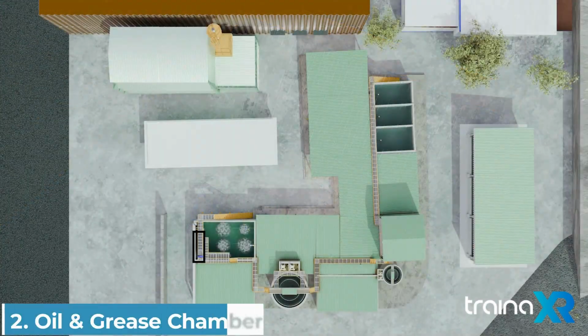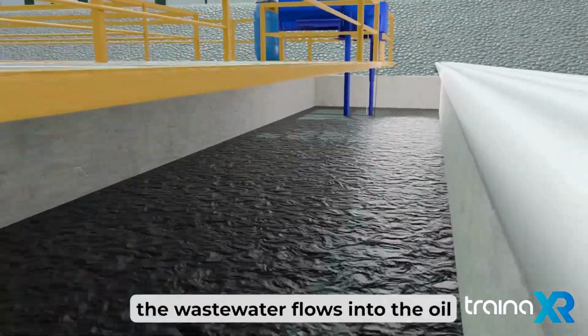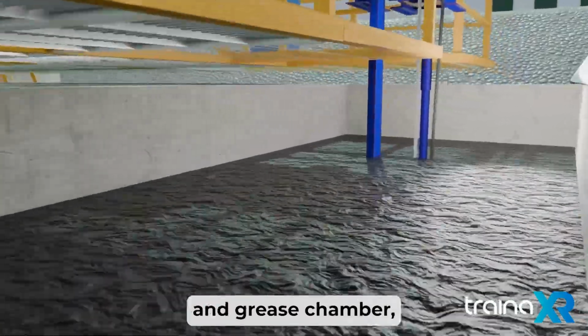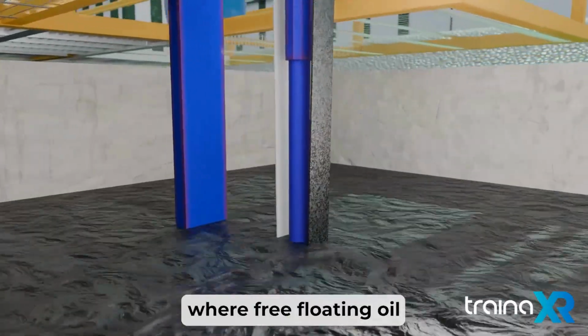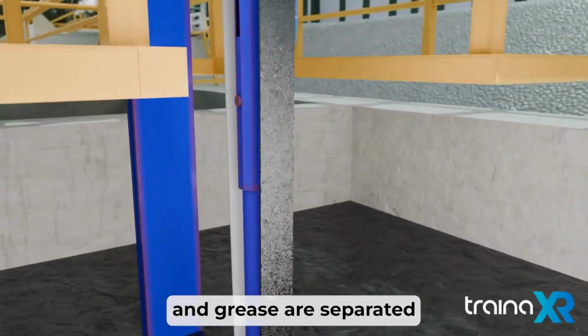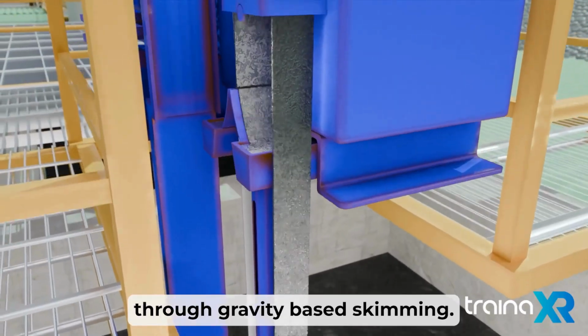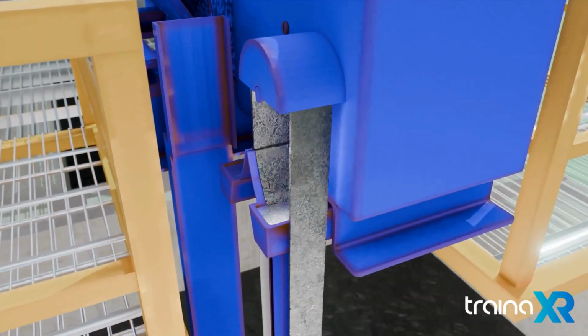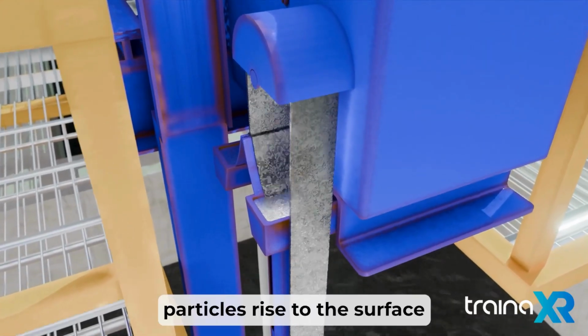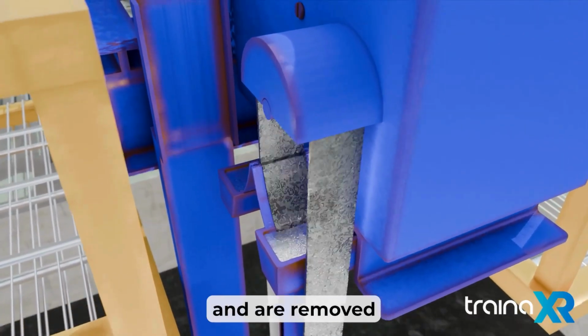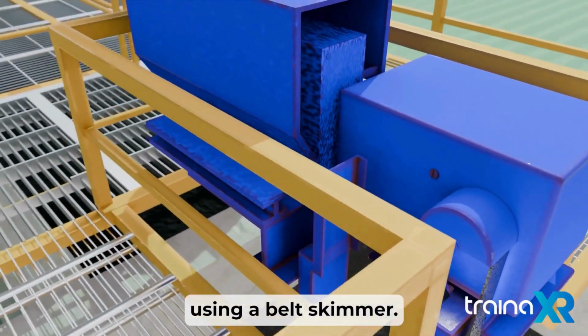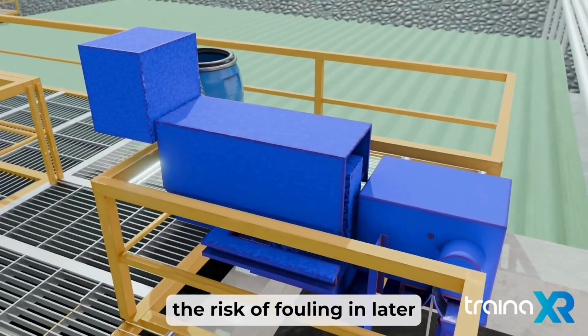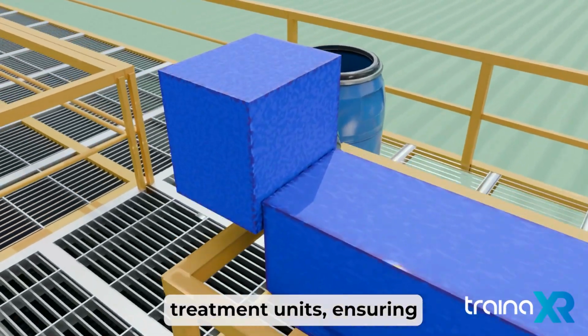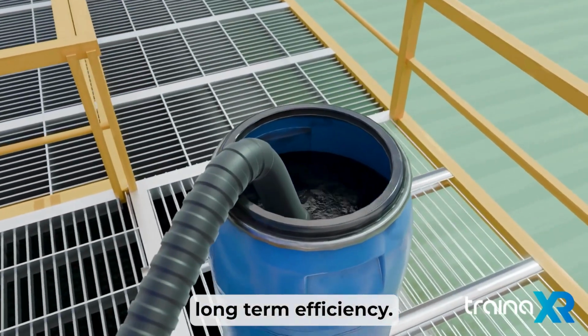Oil and grease chamber. After screening, the wastewater flows into the oil and grease chamber, where free-floating oil and grease are separated through gravity-based skimming. The lighter oil particles rise to the surface and are removed using a belt skimmer. This step reduces the risk of fouling in later treatment units, ensuring long-term efficiency.